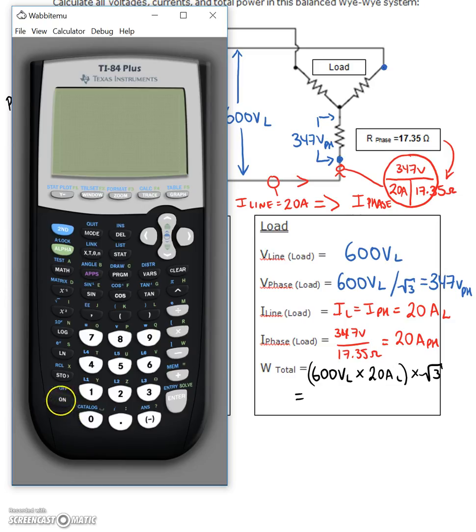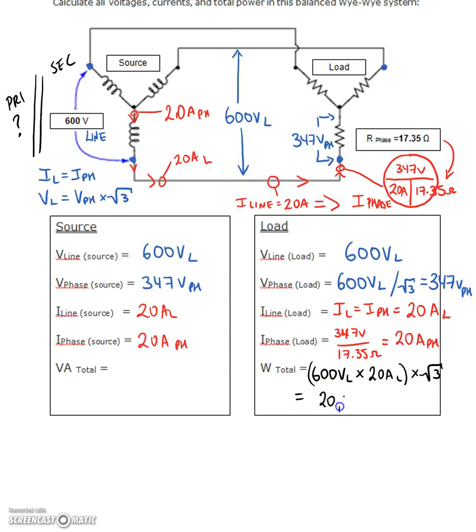So what do we've got? We've got 600 volts times 20 amps times the square root of three. That gives me 20,784.6 watts. I'm just going to put watts here because these are resistive loads.